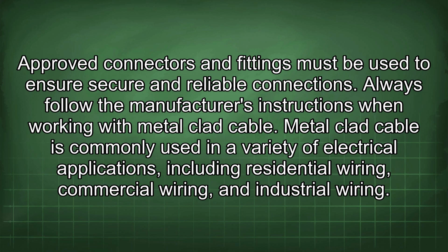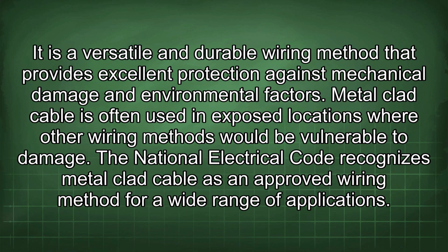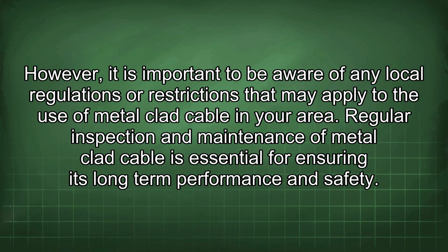Metal-clad cable is commonly used in a variety of electrical applications, including residential wiring, commercial wiring, and industrial wiring. It is a versatile and durable wiring method that provides excellent protection against mechanical damage and environmental factors. Metal-clad cable is often used in exposed locations where other wiring methods would be vulnerable to damage. The National Electrical Code recognizes metal-clad cable as an approved wiring method for a wide range of applications. However, it is important to be aware of any local regulations or restrictions that may apply to the use of metal-clad cable in your area.